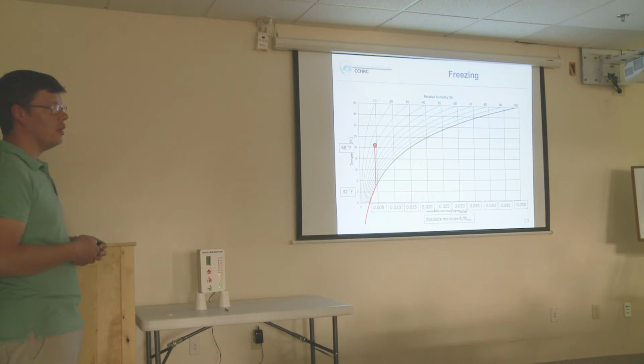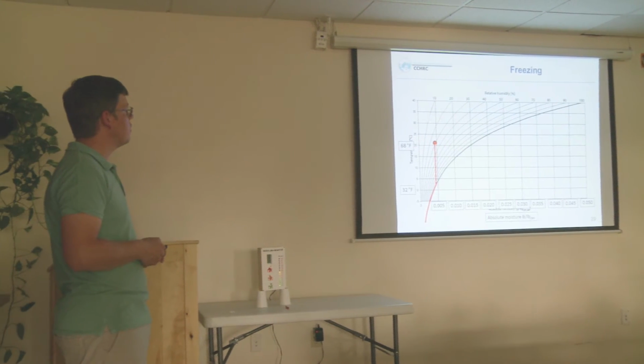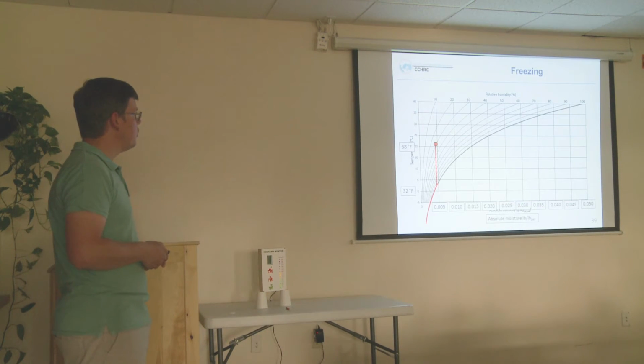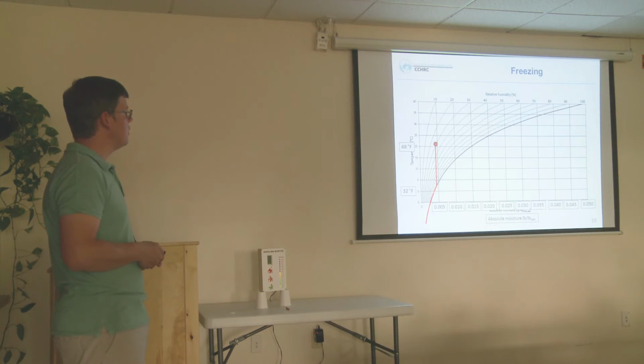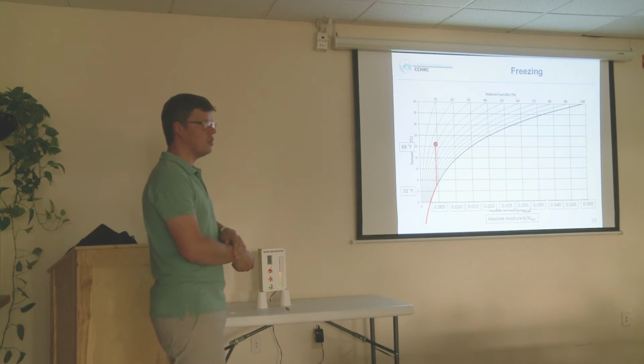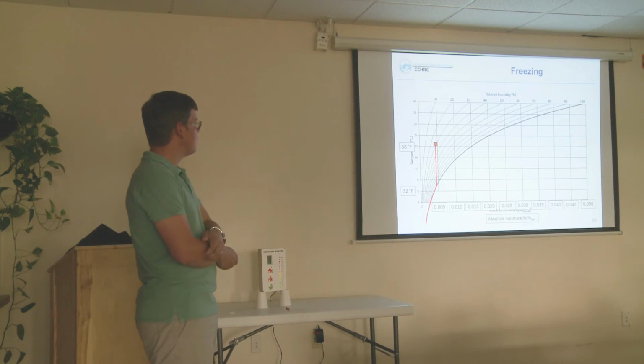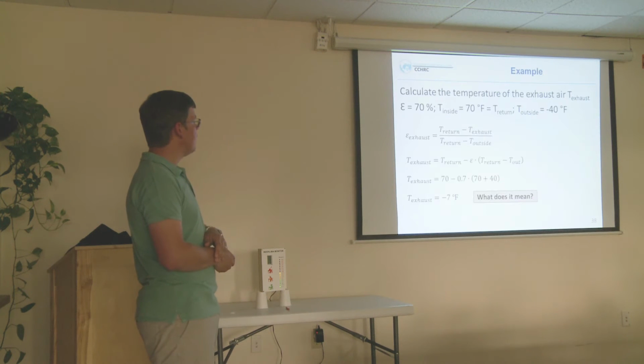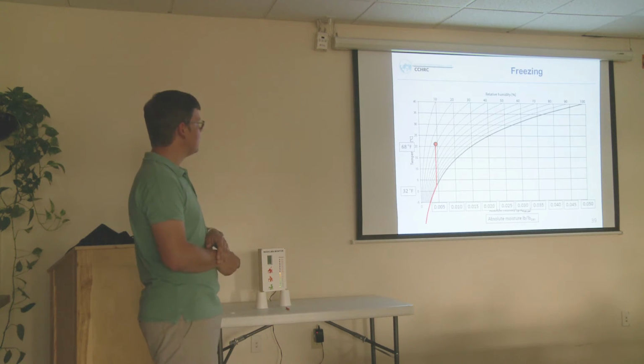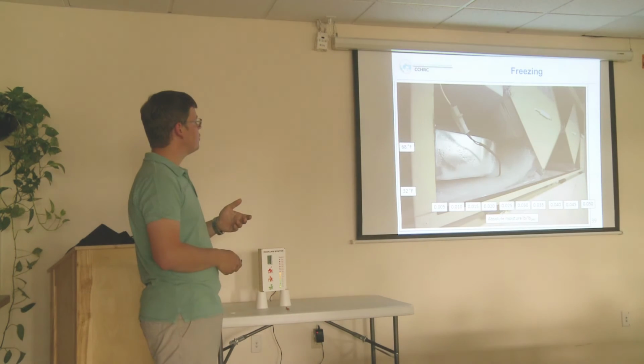And we are back to our Mollier chart. If we have 70 degree air and suddenly it starts cooling down in the heat exchanger, it hits the dew point, which is still above freezing, so that's relatively okay. That's where the condensation starts inside the heat exchanger. But then suddenly we reach the freezing region, and now all the condensation is basically frost formation. It doesn't condense anymore; it transforms directly into an ice layer in the heat exchanger. So we actually never get to that minus 7 Fahrenheit, because we have to protect the heat exchanger against this, because if we don't, then eventually the whole heat exchanger will turn into this.